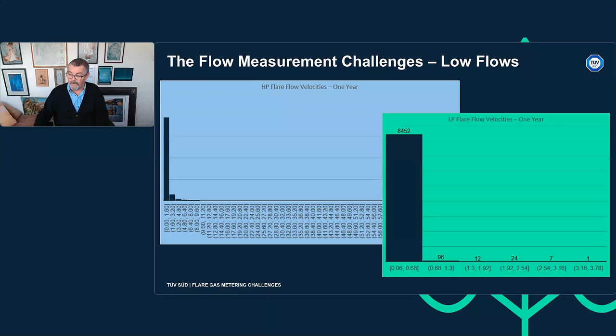Now, from a measurement perspective, that's extremely concerning, extremely challenging. If I look at a typical example here, a typical DCS analog input that has an uncertainty of 0.2% of span, up at 20 or 40 or 60 meters per second, the uncertainties are very low. And if I look at a high quality ultrasonic meter with a stated manufacturer uncertainty of 0.1 meters per second, again, at 20, 40, 60 meters per second, everything's fine, very low uncertainties. If I'm trying to minimize my gas flows, well, let's look at what happens when I zoom into the lower flow velocities.